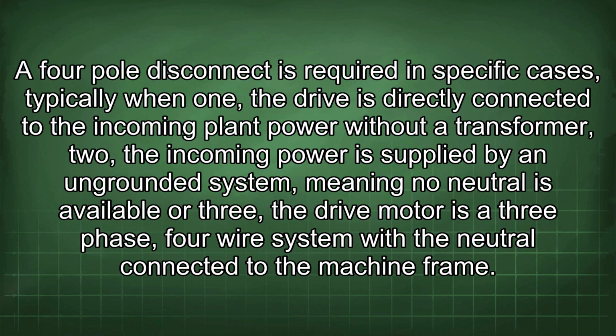A 4-pole disconnect is required in specific cases, typically when: 1. The drive is directly connected to the incoming plant power without a transformer. 2. The incoming power is supplied by an ungrounded system, meaning no neutral is available. Or 3. The drive motor is a 3-phase, 4-wire system with the neutral connected to the machine frame.